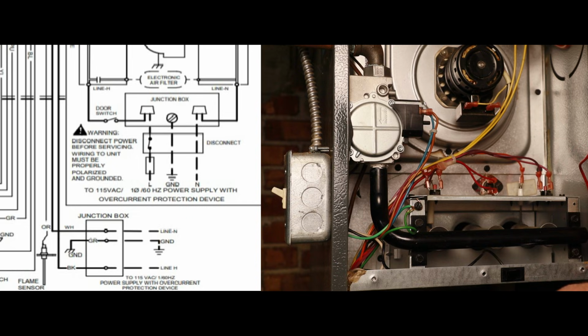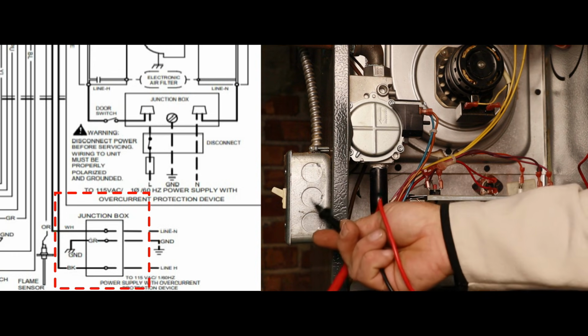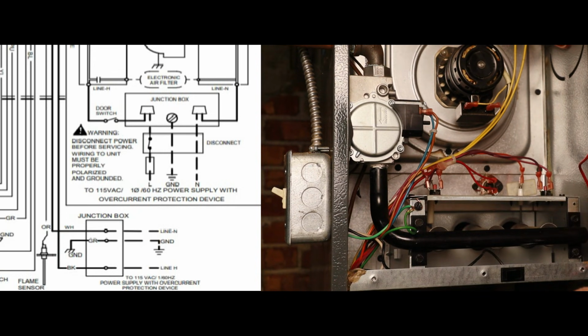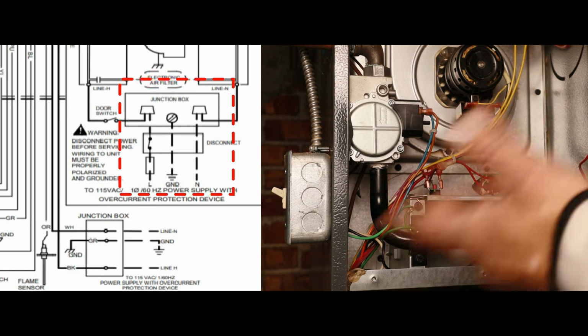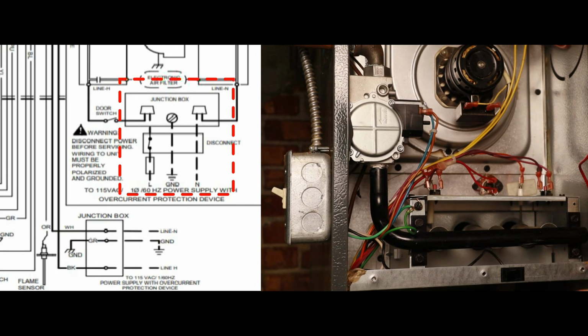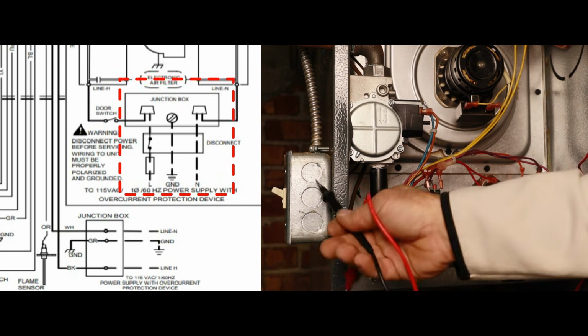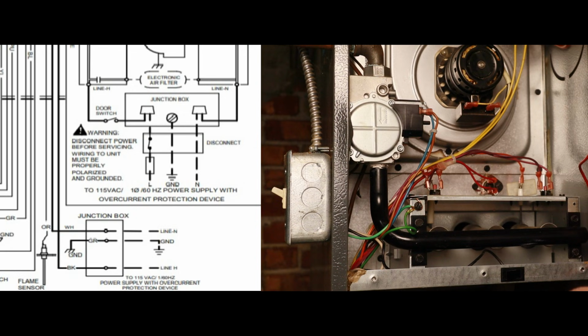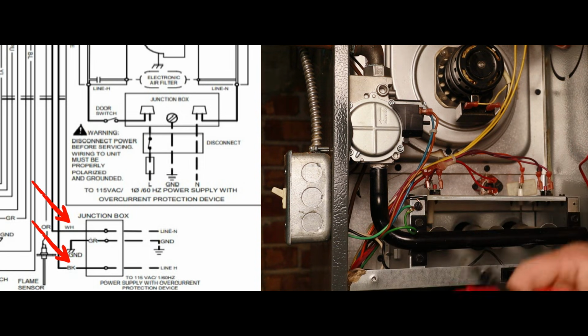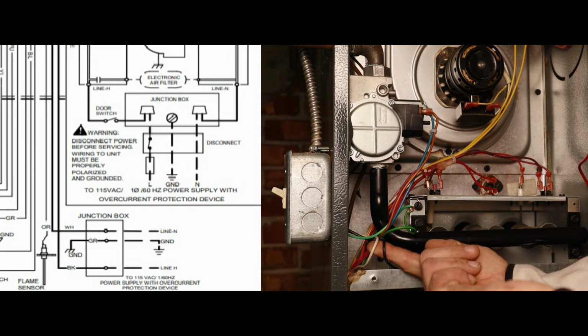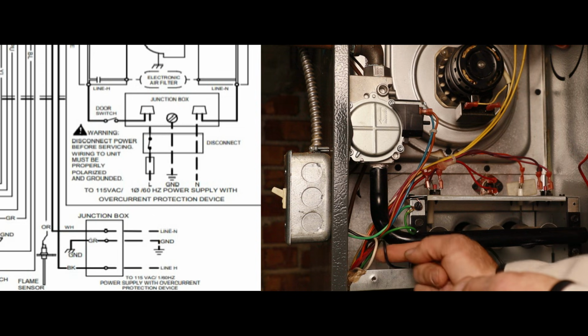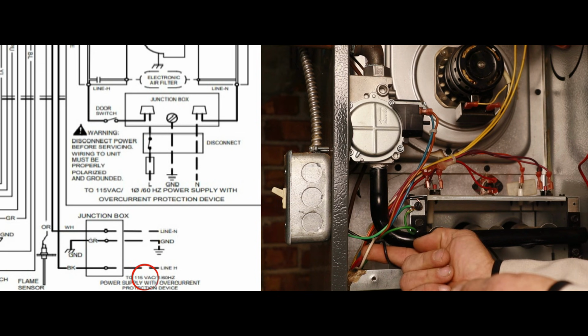So the first thing I like to do whenever I'm looking at a schematic is I always look for the power source coming in. So on our full schematic, we can see junction box, and that is actually our switch right here on the side of the unit. When we look at our diagram, we see disconnect and then junction box. That disconnect is basically the breaker back at the main panel, the electrical panel. So the junction box on our ladder diagram is the same thing. It is our switch here. So going back to our full diagram, we see we have a black wire and a white wire coming off of this switch. And when we look at the wiring coming into the unit, that's exactly what we find right here. Our black is 120 volts and our white is our neutral.